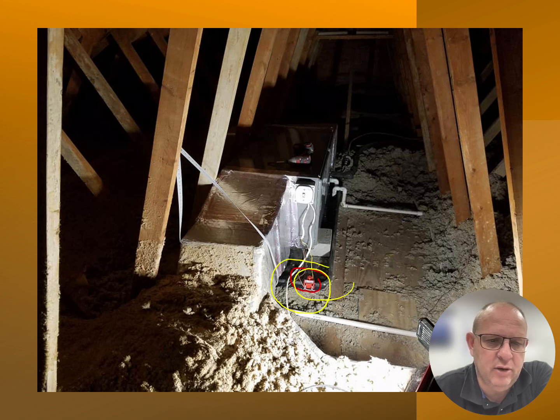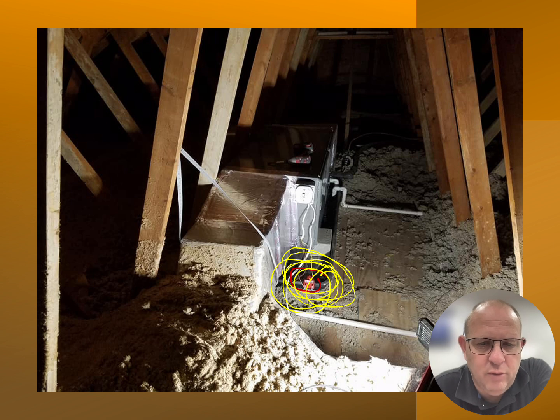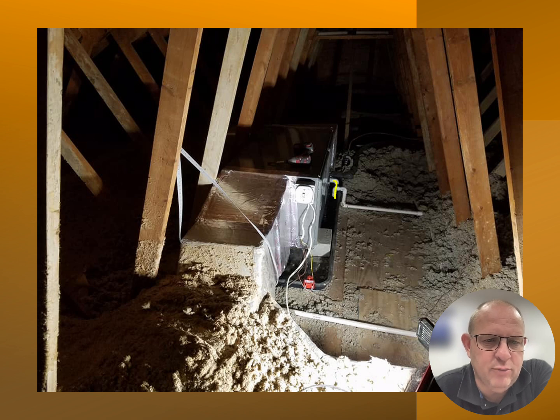If the auxiliary drain pan was to overflow, this switch would shut off the air conditioner to prevent any more condensation from getting to that point. Right before it overflows is when the switch should go off on the unit itself. Condensate drain running here is going to be running to the outside of the house. Notice that the condensate drain for the auxiliary drain pan is not hooked in with the primary drain.